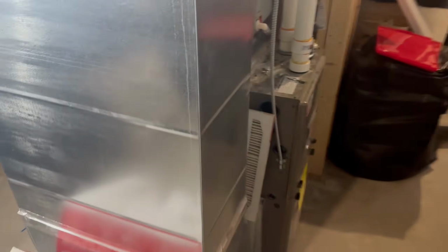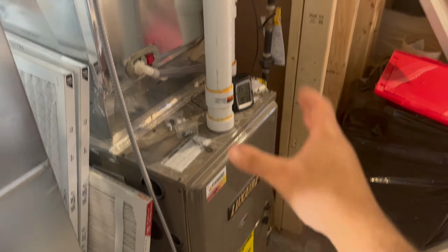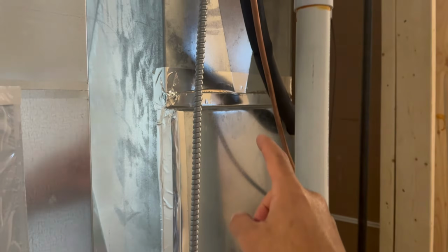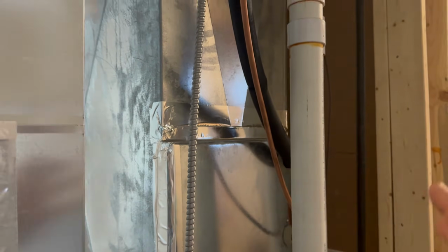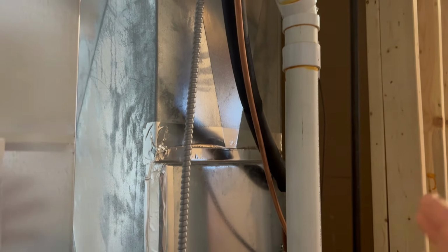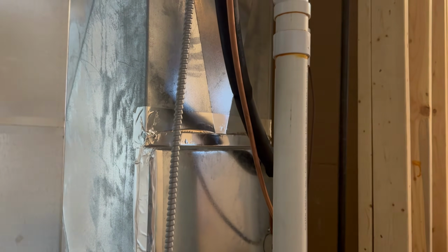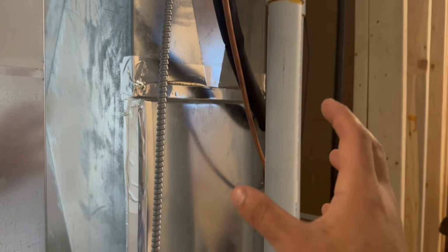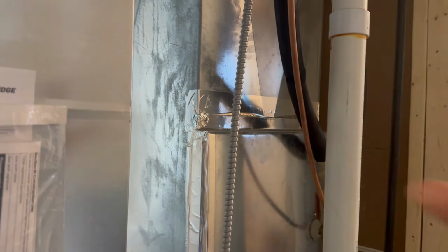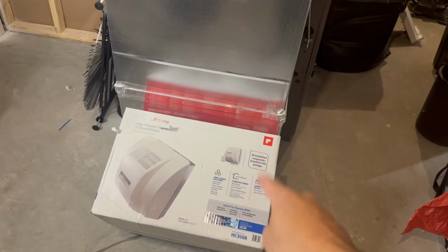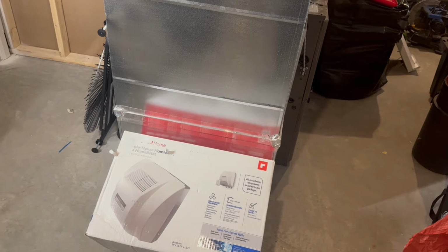So that means if you've got a furnace that's sitting vertically like this, you want to mount yours on the supply side. This goes directly to the house, which means it's a lot less work for the humidifier to just take that air using the fan and push it through into the supply side of the home. So if you've got direct fan powered, that goes on the supply side.